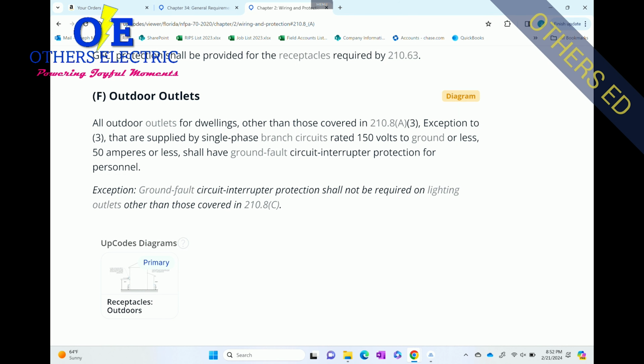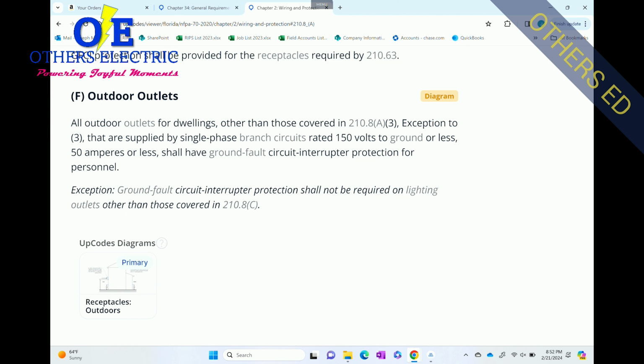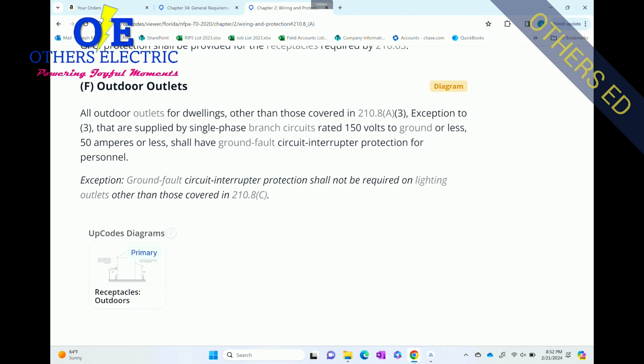Single phase branch circuits rated 150 volts to ground or less. So that's everything in a house. Everything in a house is going to be 150 volts to ground or less, all of it, okay? And then it says 50 amps or less. So if it's a 50 amp, 30 amp, 20 amp, 15 amp, it's included in here. Shall have ground fault circuit interrupter protection for personnel.